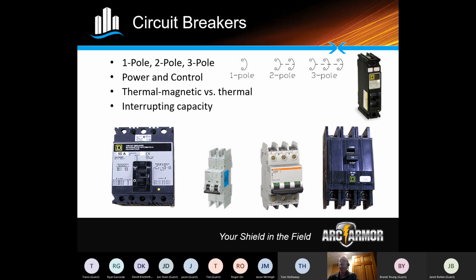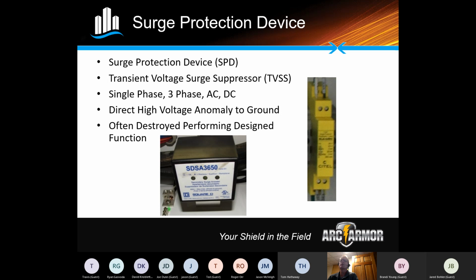All right, moving on. Surge protection devices. I'm going to throw all my items up here as well right away. Years ago, everybody called them transient voltage surge suppressors, or TVSS. The latest buzzword now is surge protection device. They're one and the same, right? So it was kind of a little bit of a trick: is there a difference between the two? According to the NEC and UL now, they are both the same thing. So surge protection device is going to be the main name that you're going to be hearing going forward. TVSS may still be thrown out there, but I just wanted to make sure everybody knows that they're one and the same thing.